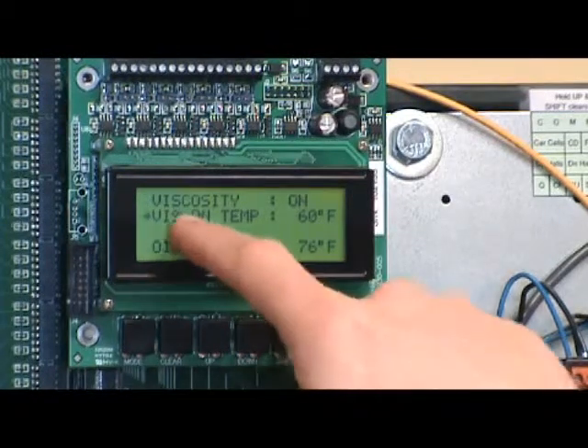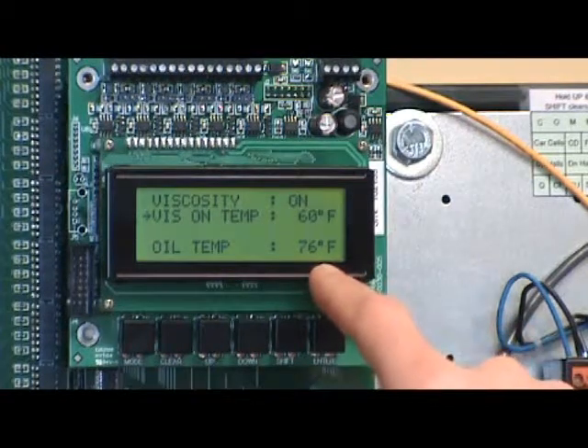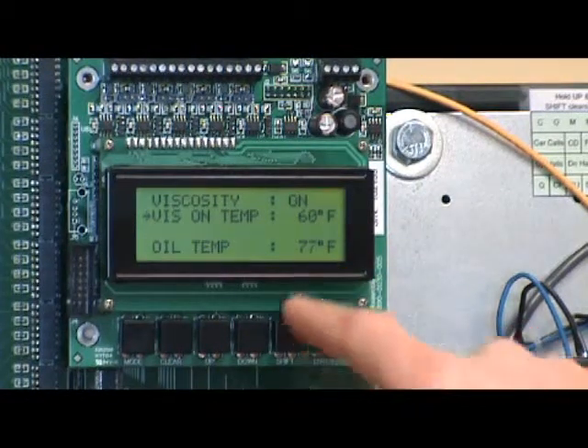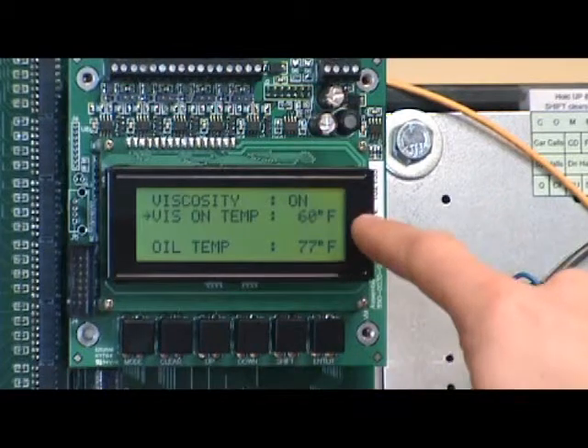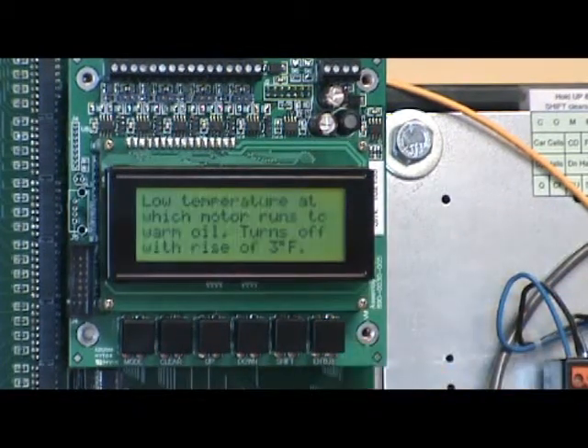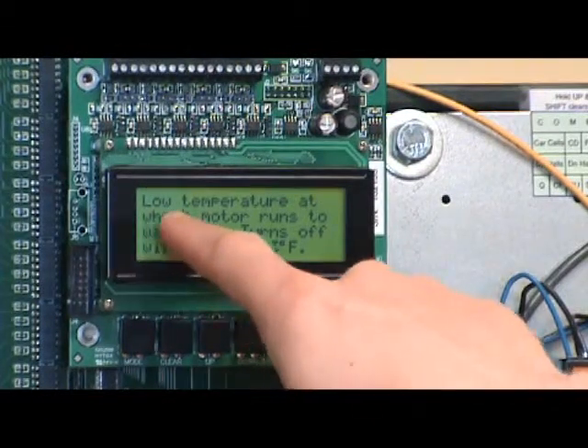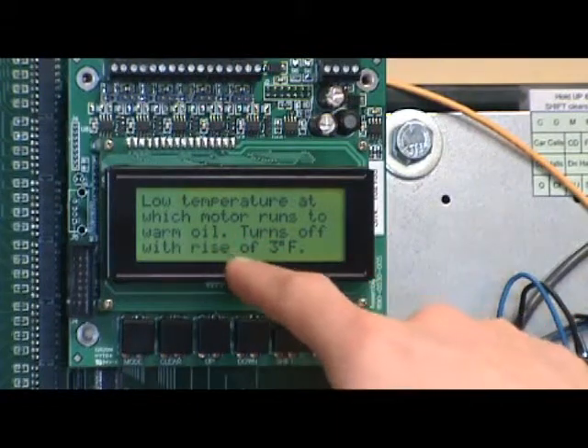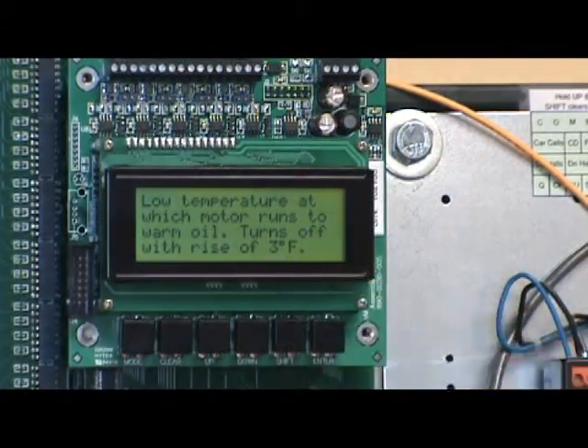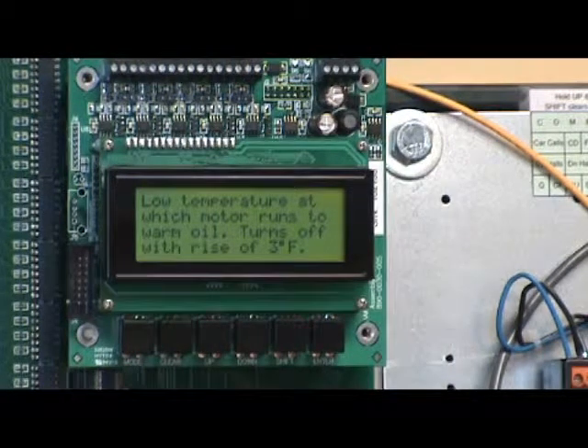If you scroll down now, it's going to give you the option of what do you want to set the viscosity temperature for. At this point, if you hit the shift button, it's going to flash that question mark. If you hit enter, it's going to give you a little description of what that temperature reading is going to do. When the oil hits that temperature, what's going to happen. Right here it says a low temperature at which the motor runs to warm oil turns off with a rise of 3 degrees. So if you set that setting, it's going to run the pump and not open the valve. It's going to run the pump and bypass oil until the oil temperature increases 3 degrees, or a maximum run time of 5 minutes.